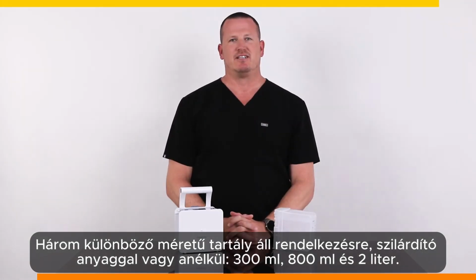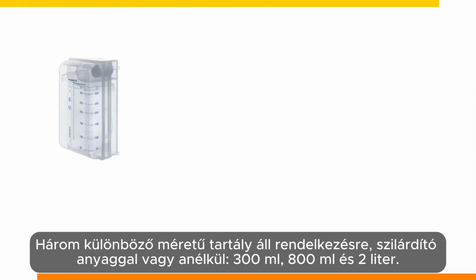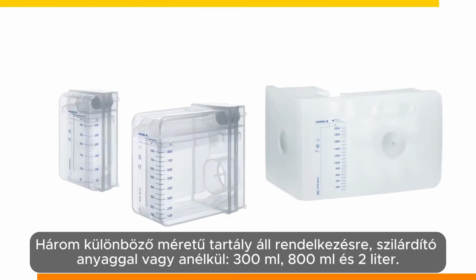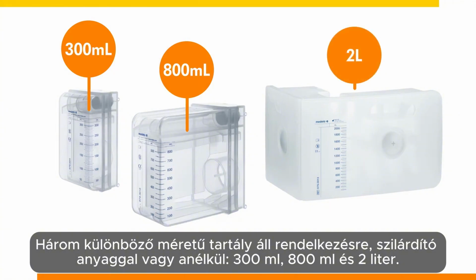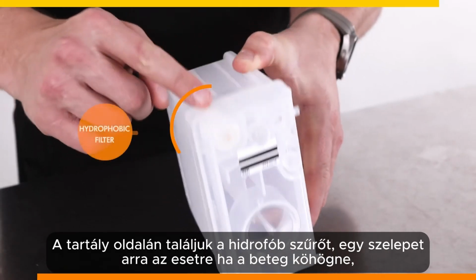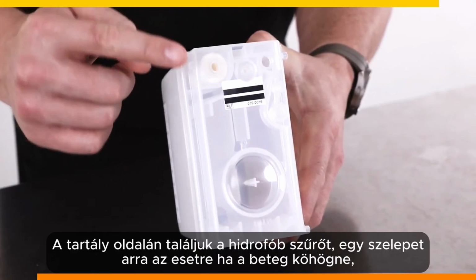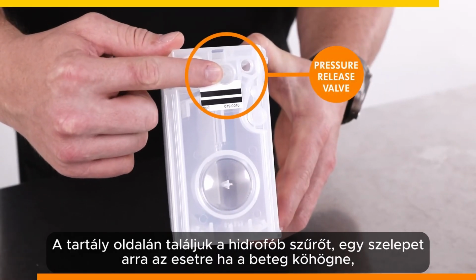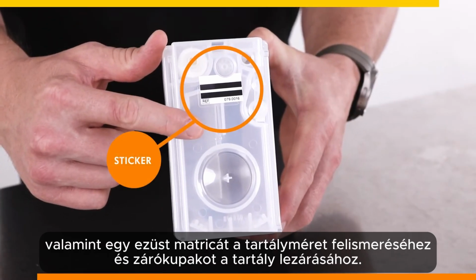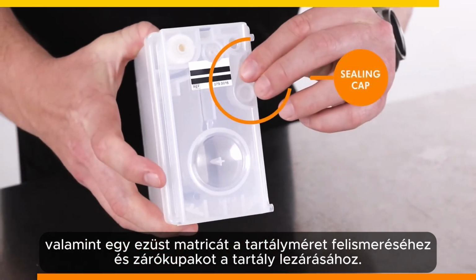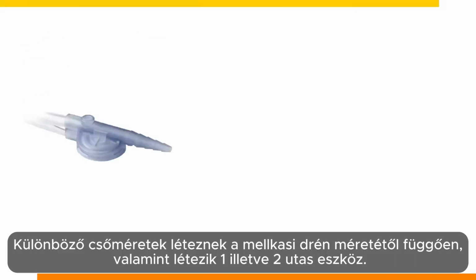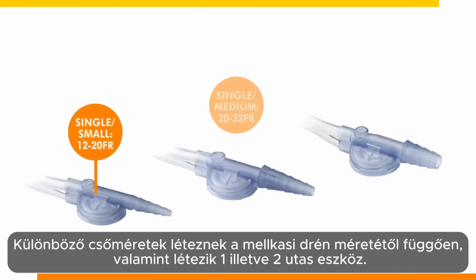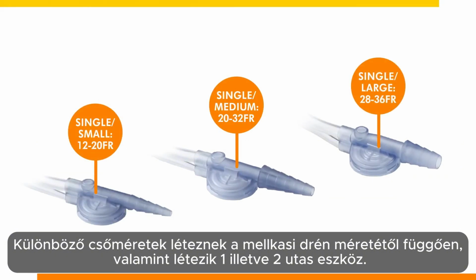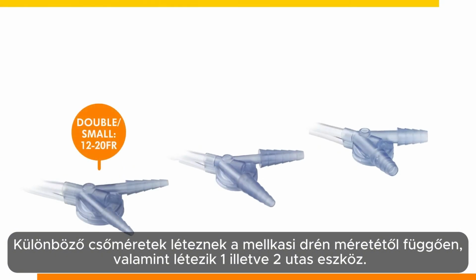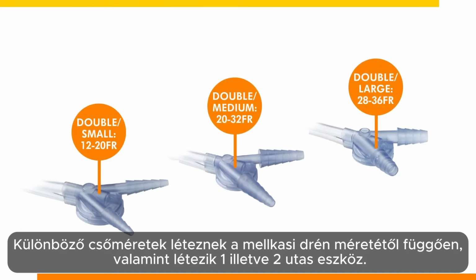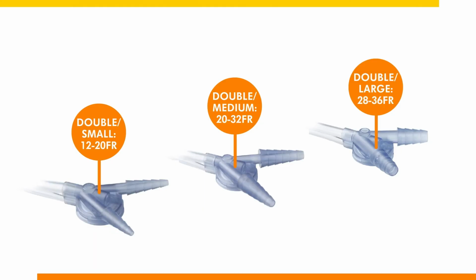So back to the canister. There are 3 different sizes of canister available with or without a solidifier: 300 milliliter, 800 milliliter, and 2 liter. Each canister is equipped with a hydrophobic filter to prevent overflow, a pressure release valve in case the patient coughs, a sticker for canister size detection, and a sealing cap to seal the canister prior to disposal. There are different tubing sizes depending on the size of the chest drain, and you can connect multiple chest tubes unilaterally to the device by selecting a double connector and tubing extension set. These are contained individually in sterile packaging.